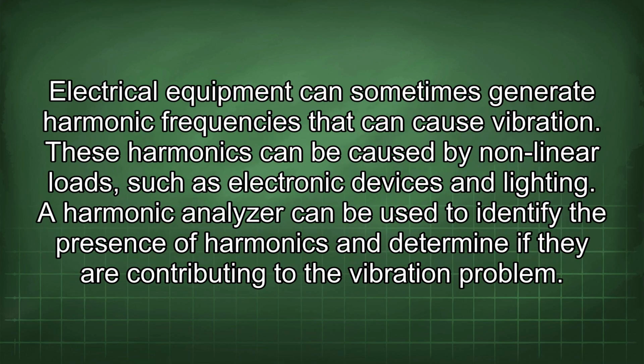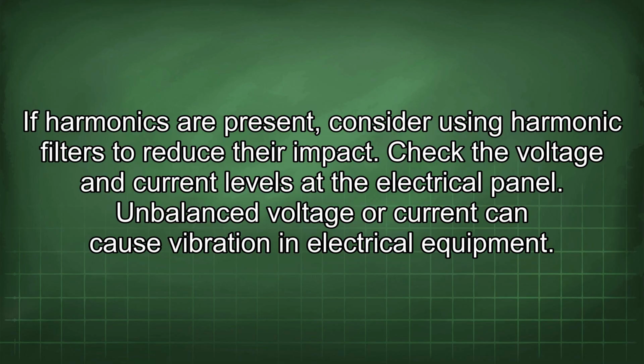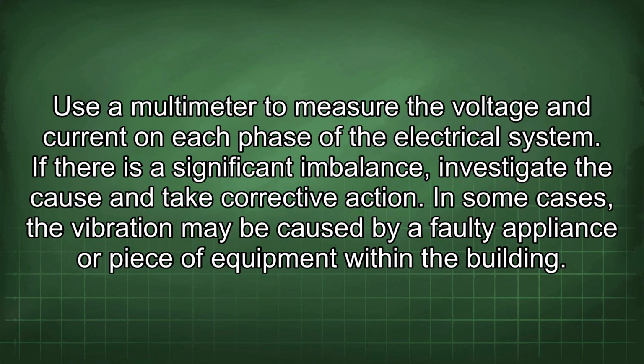Electrical equipment can sometimes generate harmonic frequencies that can cause vibration. These harmonics can be caused by nonlinear loads such as electronic devices and lighting. A harmonic analyzer can be used to identify the presence of harmonics and determine if they are contributing to the vibration problem. If harmonics are present, consider using harmonic filters to reduce their impact. Check the voltage and current levels at the electrical panel. Unbalanced voltage or current can cause vibration in electrical equipment. Use a multimeter to measure the voltage and current on each phase of the electrical system. If there is a significant imbalance, investigate the cause and take corrective action.